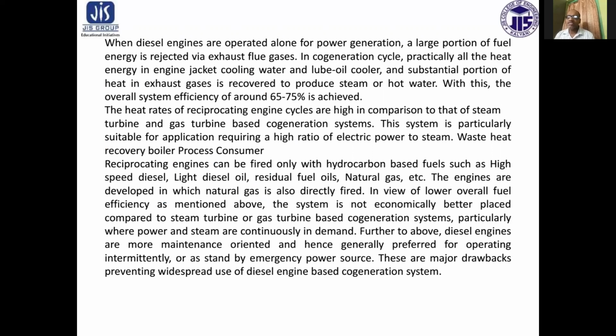When diesel engines are operated alone for power generation, a large proportion of fuel energy is rejected via exhaust flue gas. In the cogeneration cycle, practically all the heat energy in the engine jacket, cooling water, and lube oil cooler, and a substantial proportion of heat in the exhaust gases, is recovered to produce steam or hot water. With this, an overall system efficiency of around 65 to 75% is achieved.